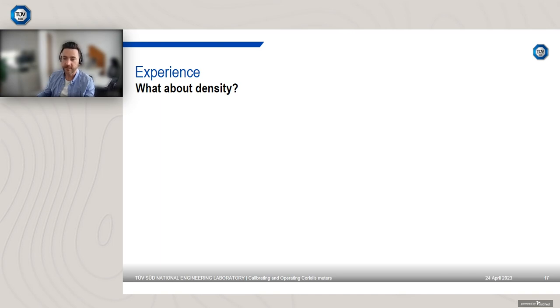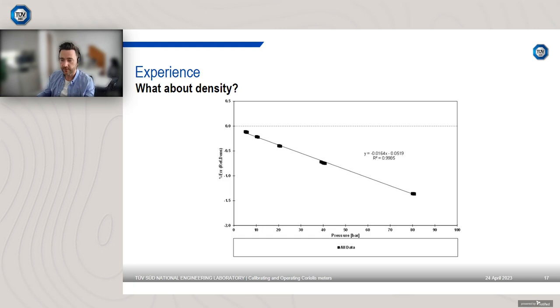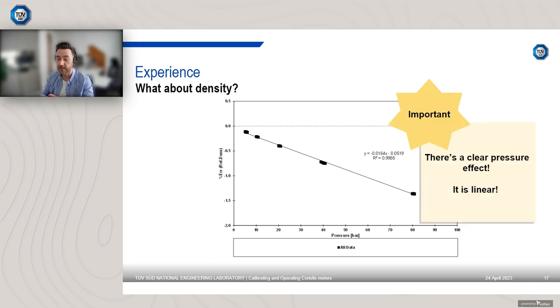Now, I don't recommend the static pressure correction, and there's a few reasons why. Very few operating conditions are static. So, for example, if you're operating at 20 bar, you might have a pressure swing of plus or minus 2 or 3 bar. Now, if you use a static correction, then you would always be correcting for, say, 20 bar, but you could then be operating at 22 bar or 18 bar if you have a 2 bar swing in pressure, which means you could be over or under correcting.